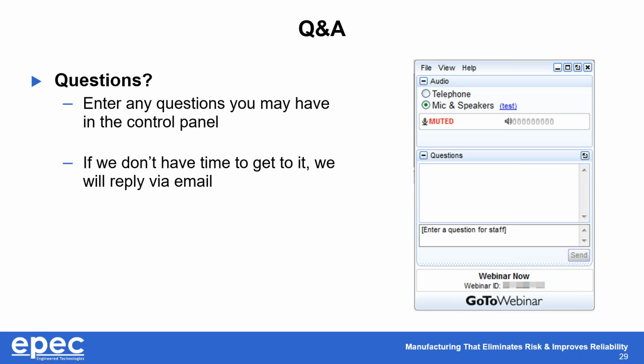Here's another one: how do you determine when the battery should be charged if it's not being used or been in long-term storage? The answer is all chemistries really self-discharge, and the BMS on the battery is going to typically draw some milliamps. So the rule of thumb is to charge batteries when you receive them if you can. If you have to store long-term, keep the batteries at approximately 50% state of charge. Check them every 6 months to verify voltage levels, and charge again if required.